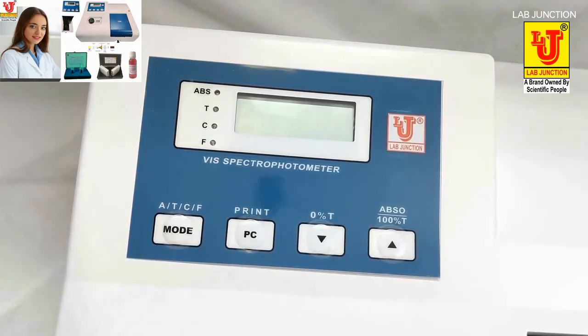We have two types of microprocessor visible single beam spectrophotometer. One is model LJ1305, this one, and its path length facility is 10 mm to 50 mm, and in model LJ1306 the path length facility is 10 mm to 100 mm. Now this instrument is model LJ1305.